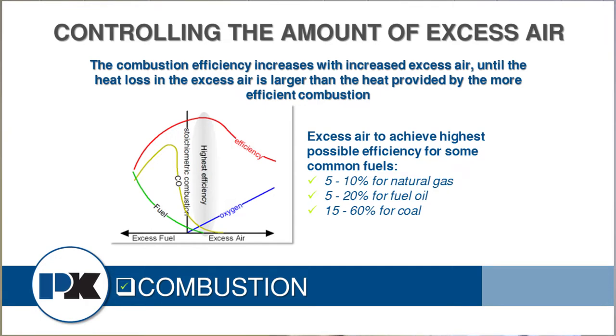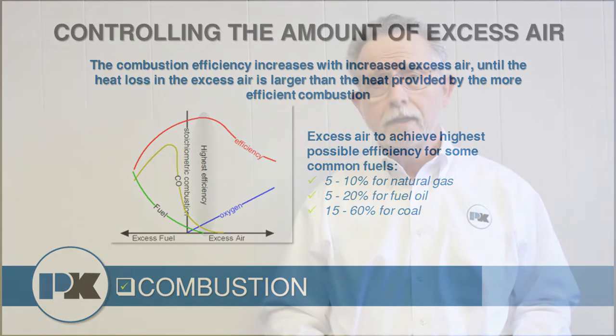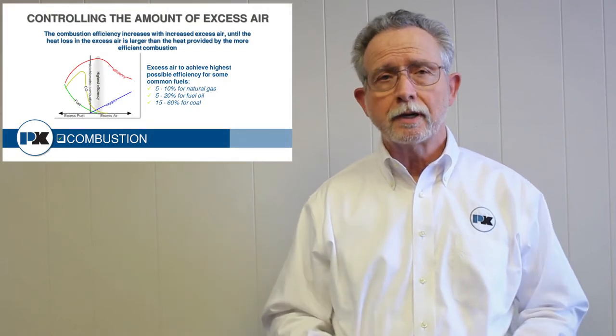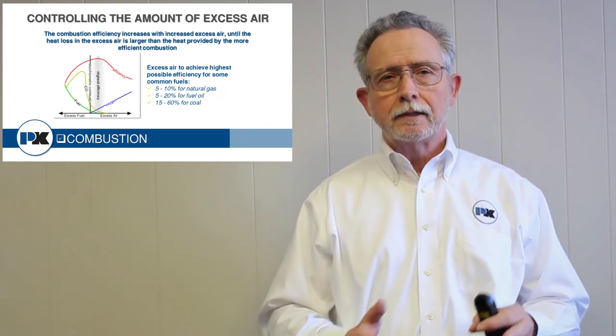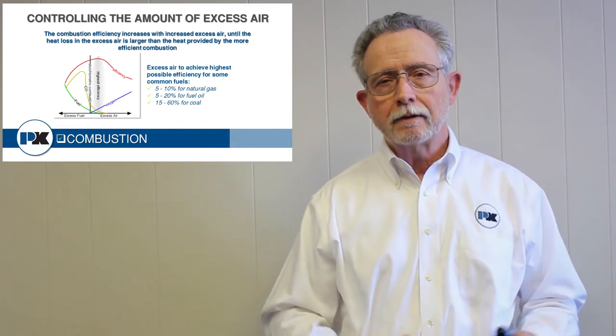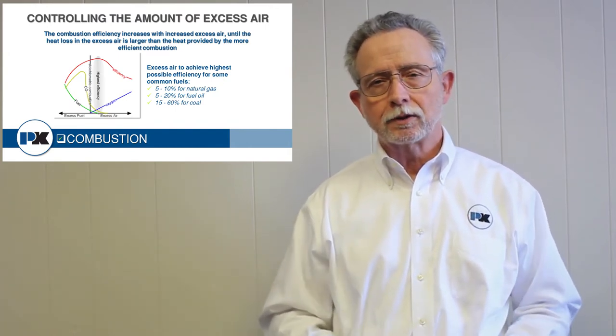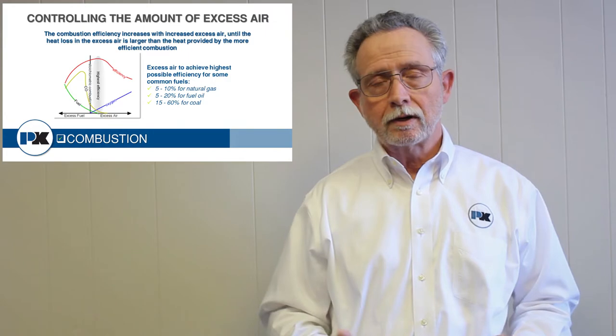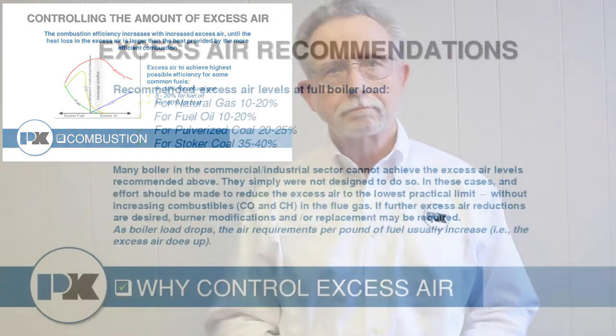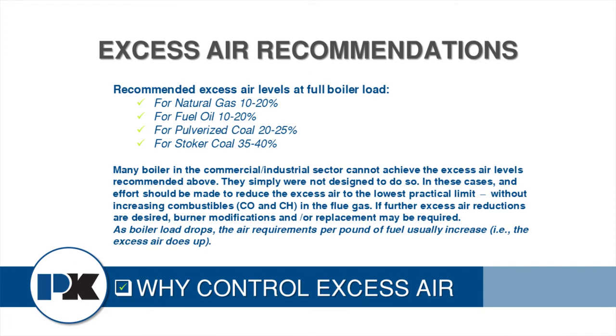The first thing we're going to look at is the amount of excess air. In the lab we could create what they call stoichiometric combustion — this is no excess air, just enough air to burn the fuel. It will not happen out in the field; there are too many variables like air being impeded, gas pressure drop, venting, and a host of other things that could affect that.